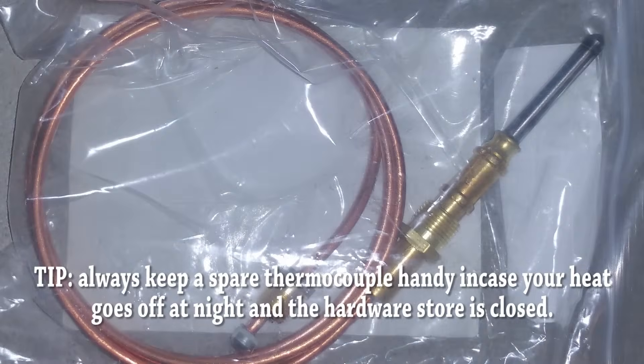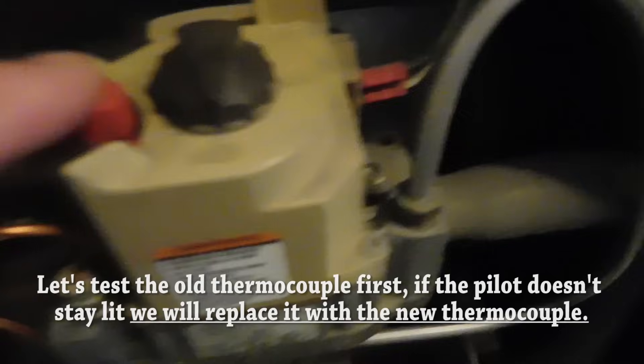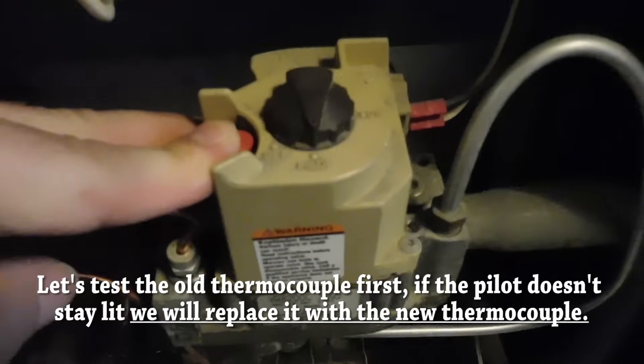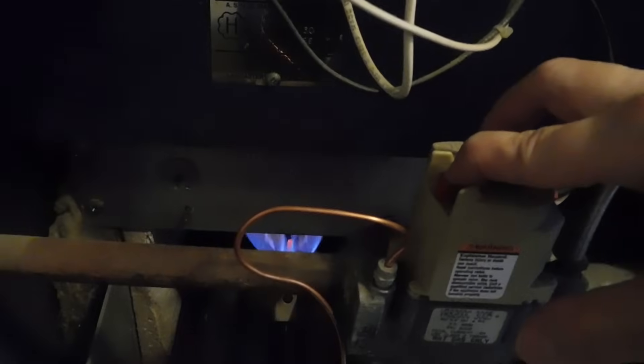This is the new thermocouple we're going to install. First, let me demonstrate the problem — there is no fire and the light is off. We'll take the heat shield out and try to relight the pilot. I set it to pilot, hold the button down, apply fire, and keep holding the pilot button down for about 30 to 40 seconds. When you let go, if the thermocouple is working it should stay on. As you can see, it's not staying on.